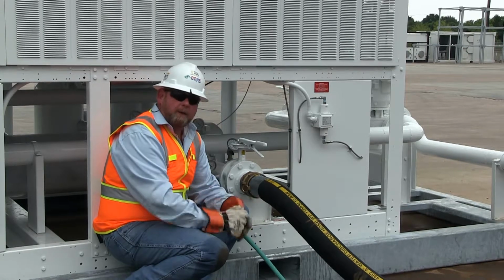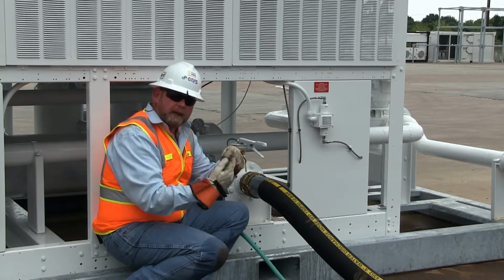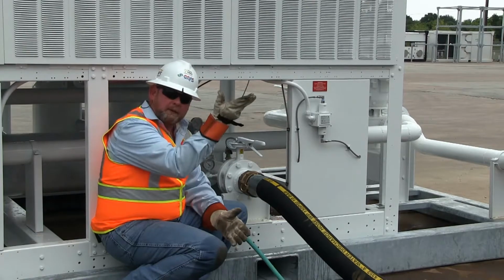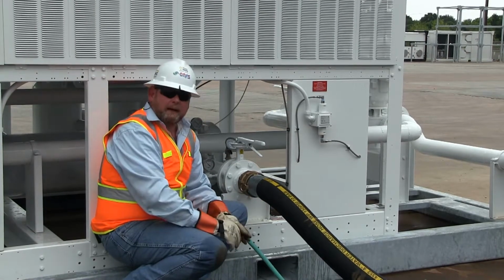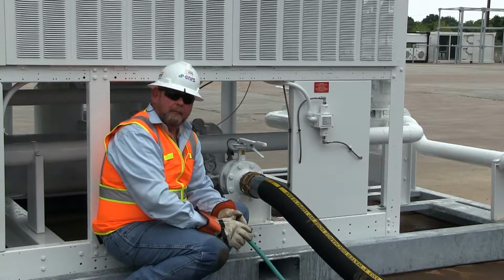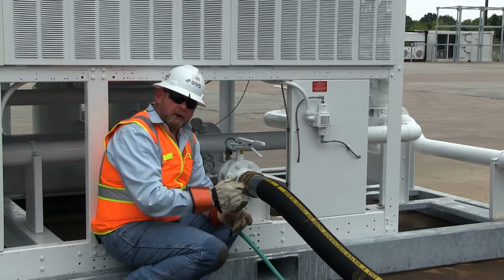So when you start with the pump, you want to just let the water circulate, let all the water fall, let all the air bubbles go to the top. You cannot get the air out as long as the pump is running, so it'll turn into foam. So that's going to be our next process. We're going to turn the pump on and bleed some more air out.